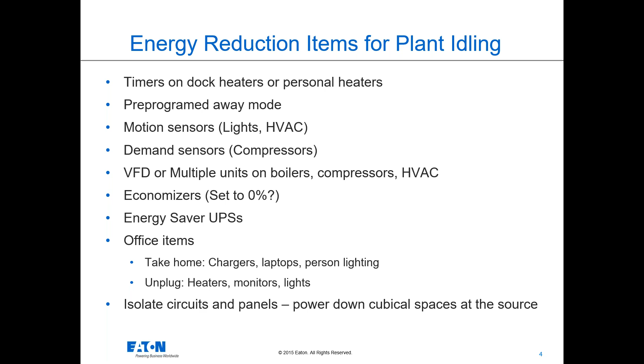The last item is isolating circuits and panels. If you've already upgraded your systems, or plan to in the near future, think about ways to isolate the things that are critical from non-critical. If you know you have a panel that's not powering anything important, you might be able to shut it all down at the circuit level. But you need to be careful - if you turn that back on and there's a high demand, you can cause more problems from a safety standpoint, so be careful with that. In general, it might be easier to isolate and control some of those office nice-to-haves on the same circuit and turn them off at a breaker.